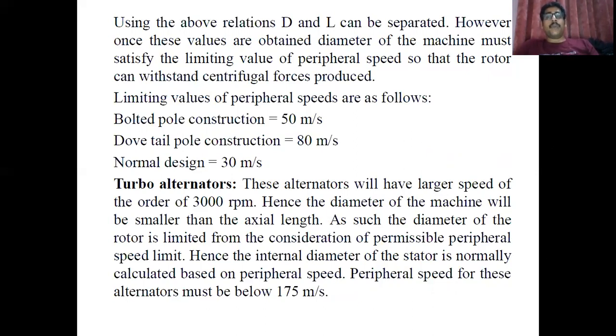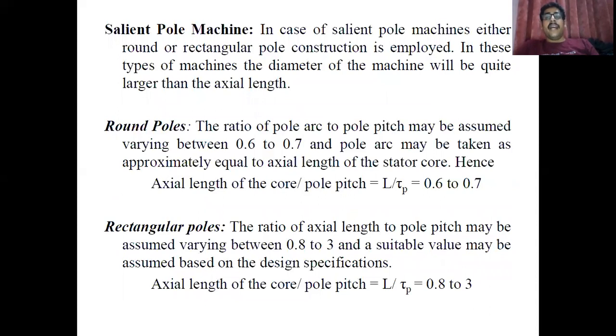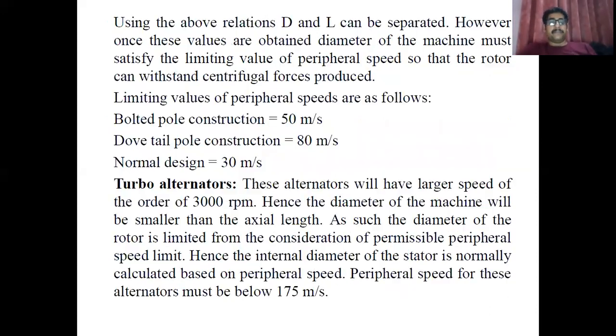Two major important things to note: Number one — if peripheral speed is given in a numerical, you use Va ≤ 30 m/s to separate D and L, where peripheral speed Va = π·D·ns and ns is the synchronous speed. Number two — if peripheral speed is not given, use the formula L/τp with a value between 0.8 to 3, depending on the machine type.